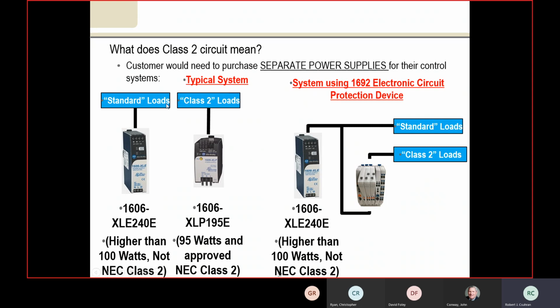In theory, you need to have a class 2 power supply for your sensors. There are other loads, and in some applications a class 2 power supply is needed for specific safety applications. I know right now that one of our drives with safe torque off does need a class 2 to meet the safety requirement. So there's another way to protect these devices. Instead of using a bunch of separate class 2 power supplies, you can use a 1692.